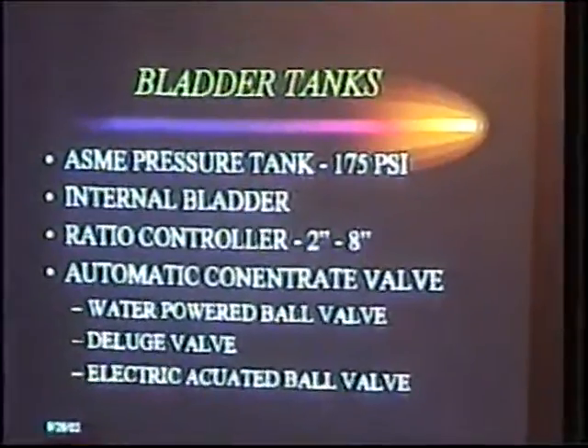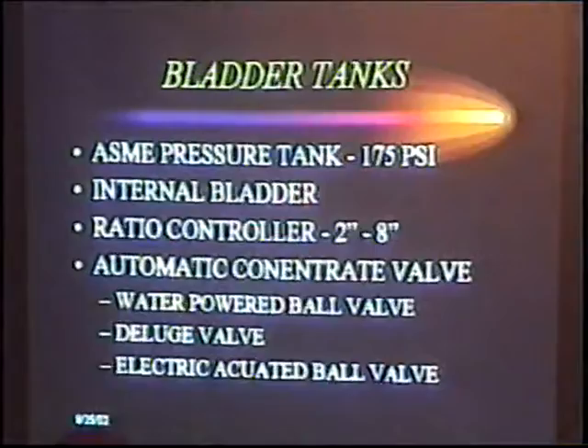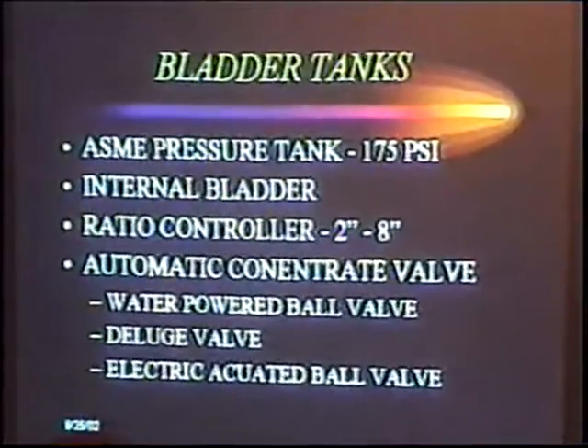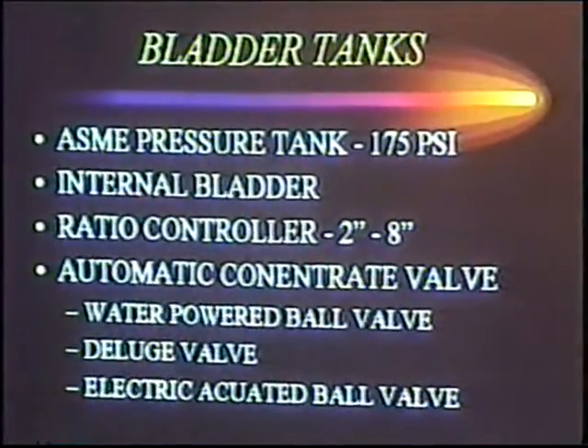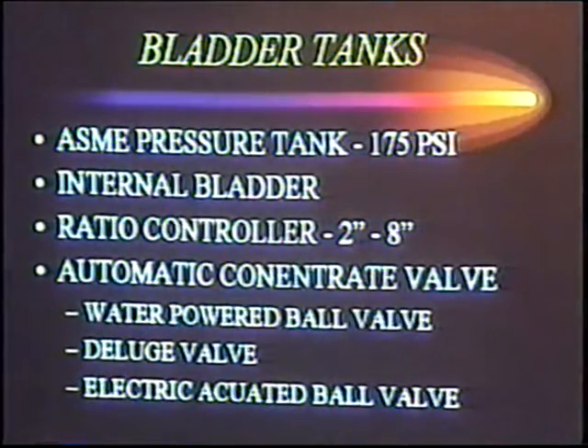Most bladder tank systems will involve what they call an automatic concentrate valve. This will be a ball valve that's located between the bladder tank and the proportioner, normally closed. You can actuate it with a water-powered actuator. Some companies use a deluge valve. Specifically, I think the Viking Corporation just uses one of the small, I think it's an H1 deluge valve, 1.5 inch, 2 inch, 2.5, which is very slick. And you can also use an electric actuated ball valve, but I don't see that as often, and I'm not a big fan of it because the power goes out.